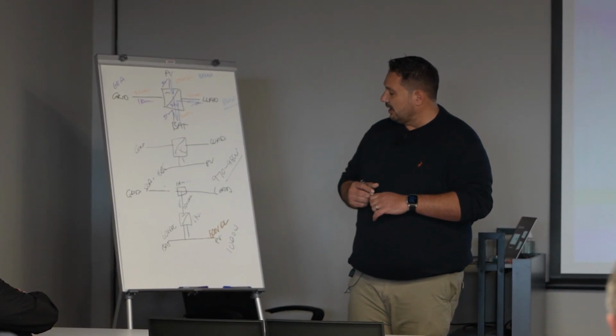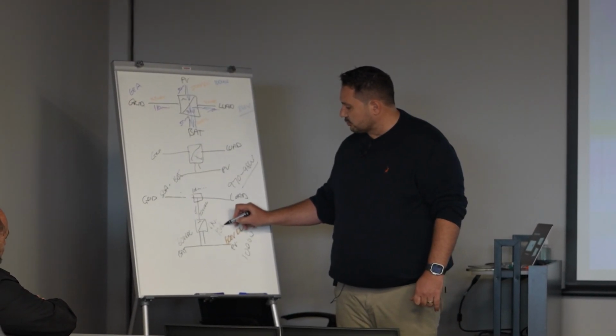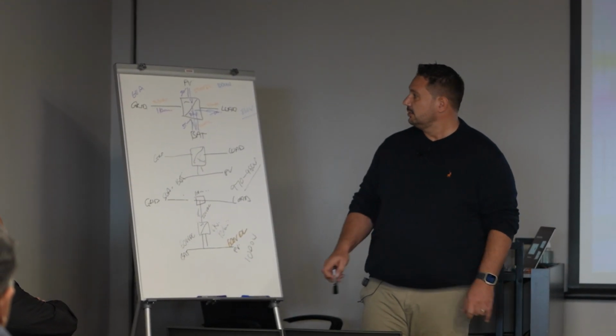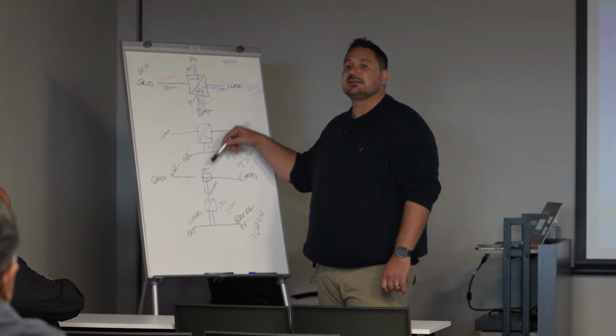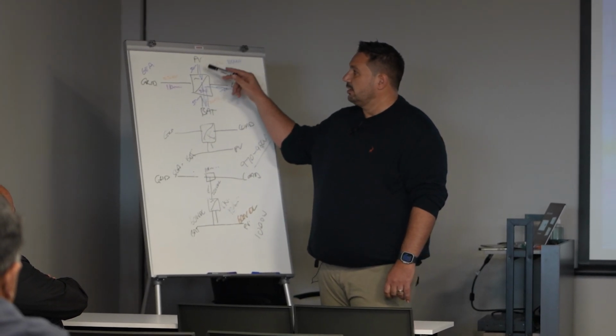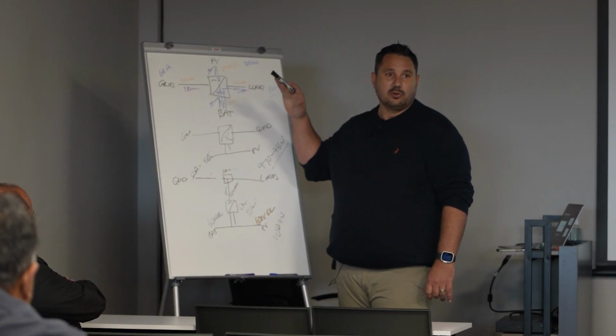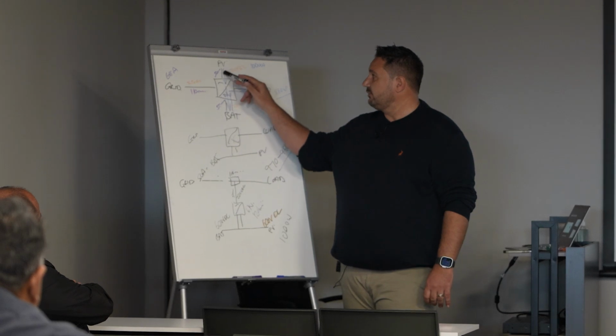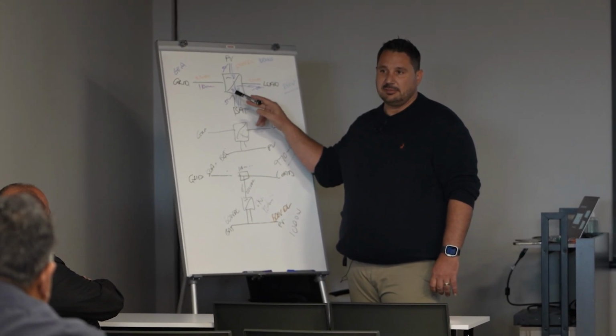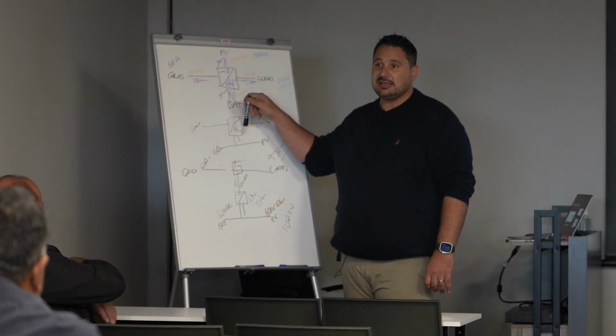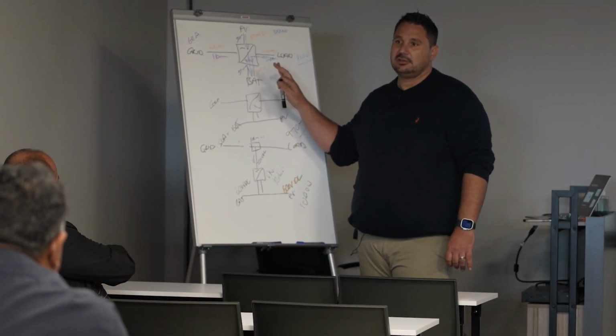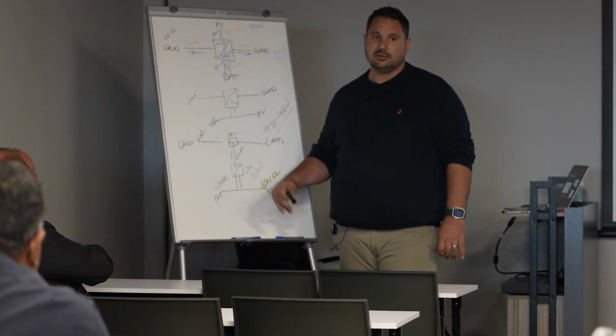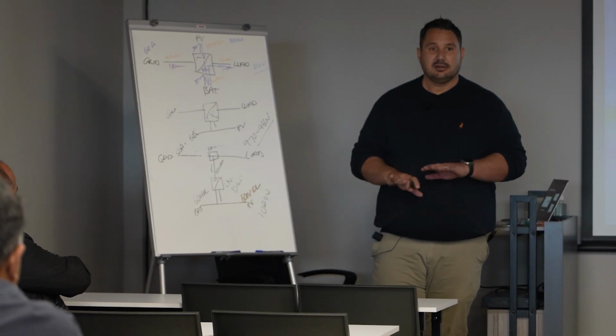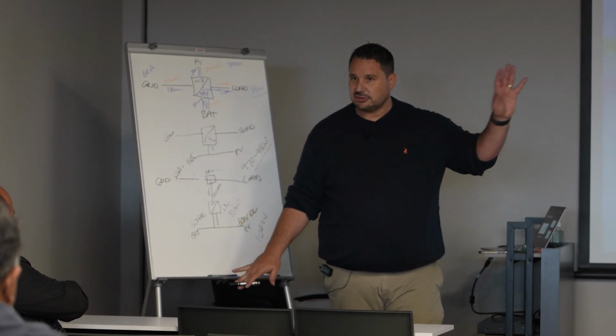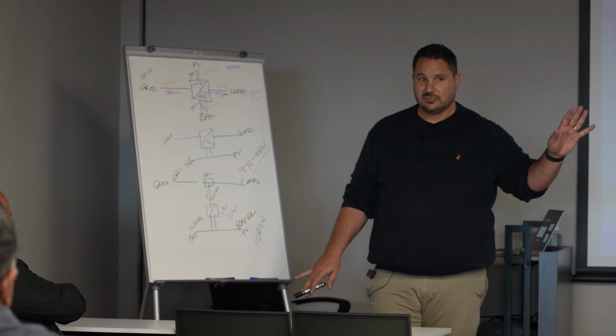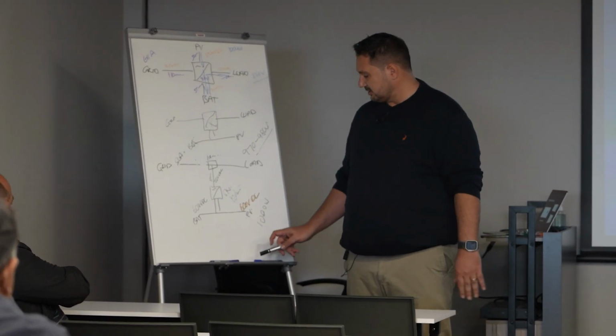The other benefit that you have is a 6 kilowatt inverter can take 12 kilowatts worth of PV, which means you can send 6 to the battery and 6 to the loads. Here you've got an 8 kilowatt full limitation. So even if you've got 10 kilowatts worth of PV here, 8 is the limit. And if you are sending 8 to the battery, 0 for load. As soon as you start taking on load, you lessen on the battery. Here, battery takes what it needs, loads takes what it needs, because you are on the same DC bus.